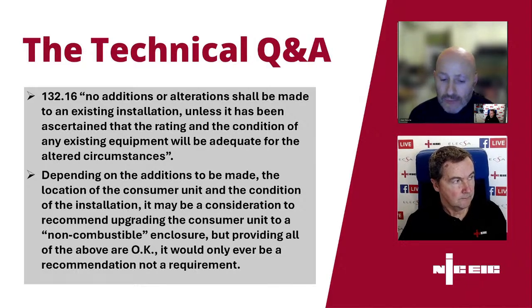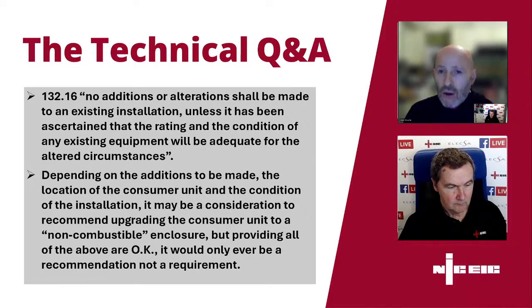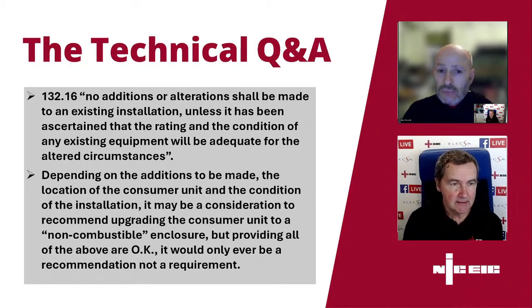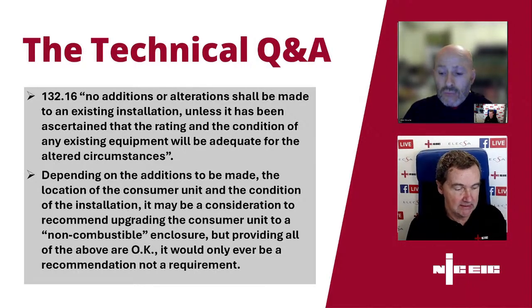Another point to raise once we've gone through that, depending on the additions to be made, the location of the consumer unit and the condition of the installation, it may be a consideration to recommend upgrading the consumer unit to a non-combustible enclosure. It's a recommendation only here. Providing all of the above are met, then it would only ever be a recommendation and not a requirement. So all the aforementioned points that are raised need to be confirmed first. But it's always good to recommend to the client, but please be mindful, it's not a requirement. It would go down to a recommendation based on the aforementioned points. Yeah, and so if, for example, it was in a sole escape route from, for example, a flat, if it was in an area of high combustion risk, then we might recommend it, even though it wouldn't be non-compliant to still continue and add the circuit.